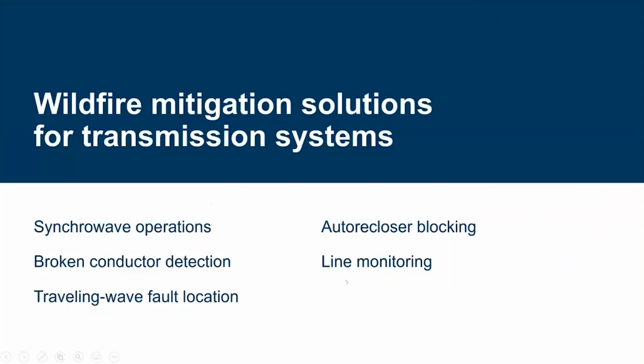So I can do line monitoring, where basically I try to find what areas of the line the faults are more common. I can also do auto reclose blocking, traveling wave fault location, which is a very accurate way of detecting the location of the fault. Then you can also use broken conductor detection, which will be added to the 400 series relays. And lastly, synchro wave operations.